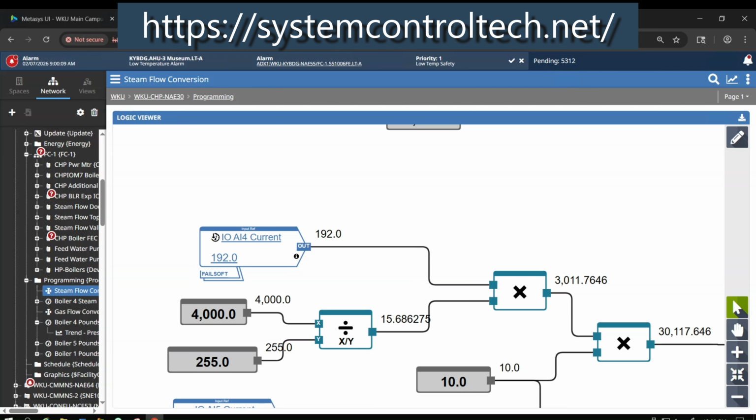Again, this signal is the maximum range that the Modbus value could be, that input for that Modbus. For BACnet, going through that translator, our maximum signal would be 0 to 255. So 0 to 4,000 for Modbus, 0 to 255 for BACnet. We need to get a constant that we can use to multiply our input to be able to get the data that we want.